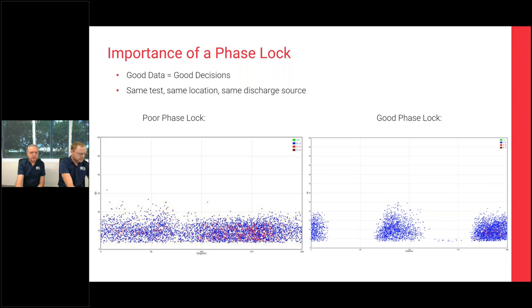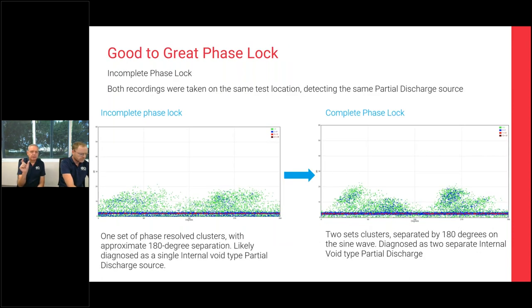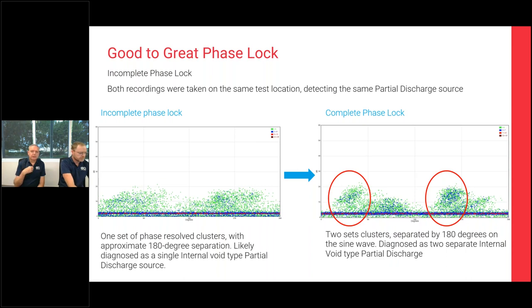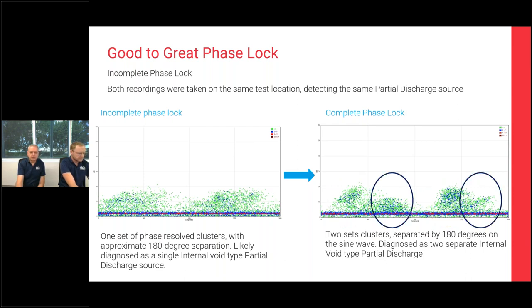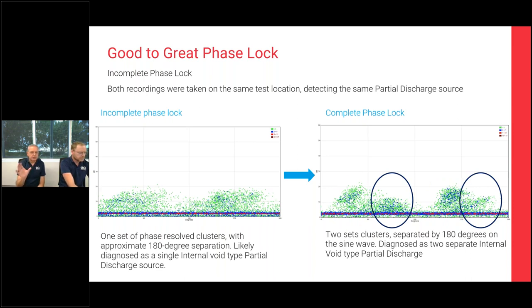Even small frequency drift matters. With a complete phase lock over the full 10-second reading, you can identify that there are two distinct clusters — one on each phase — rather than just seeing clustering at 180 degrees apart. This higher quality data enables better judgment about the type of discharge, the number of potential sources, and how many phases are involved.